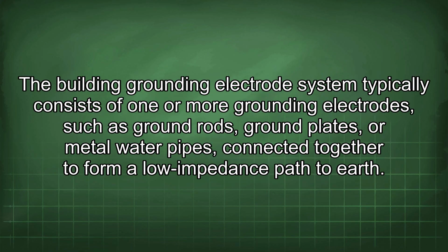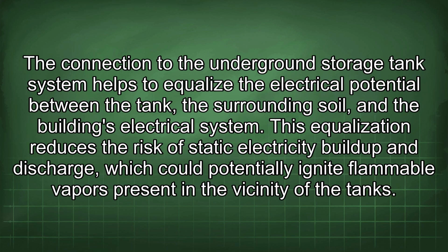The building grounding electrode system typically consists of one or more grounding electrodes, such as ground rods, ground plates, or metal water pipes, connected together to form a low-impedance path to earth. The connection to the underground storage tank system helps to equalize the electrical potential between the tank, the surrounding soil, and the building's electrical system. This equalization reduces the risk of static electricity buildup and discharge, which could potentially ignite flammable vapors present in the vicinity of the tanks.